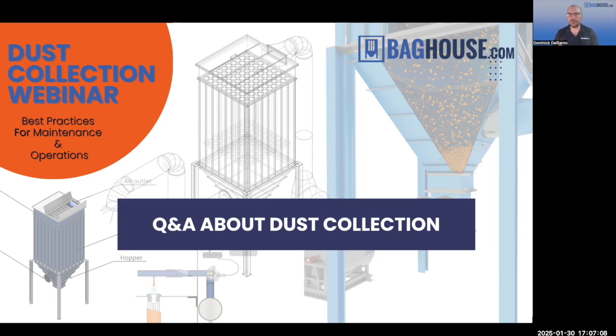But we can verify our system is too small by checking the differential pressure and how it relates to cleaning. So in a normal system, when we size it, we size the baghouse so that while you're running at full capacity, however much dust is coming into the collector can be removed by the cleaning system without having to shut down, right? So let's say 1,000 pounds per hour comes in.